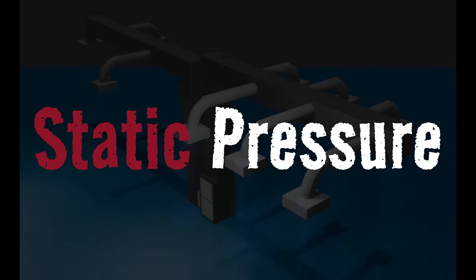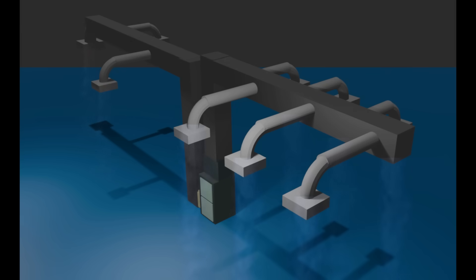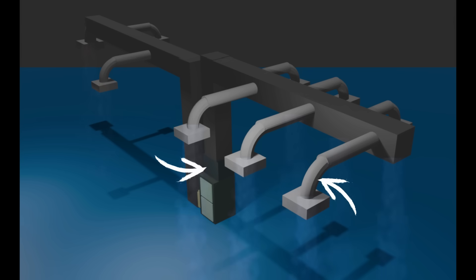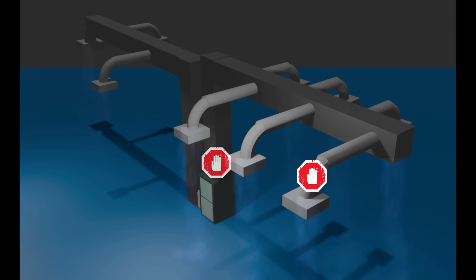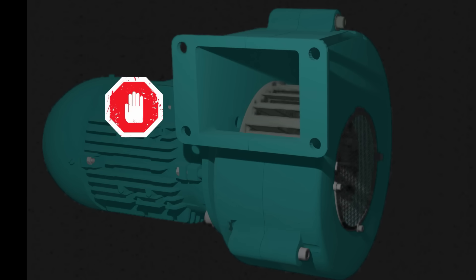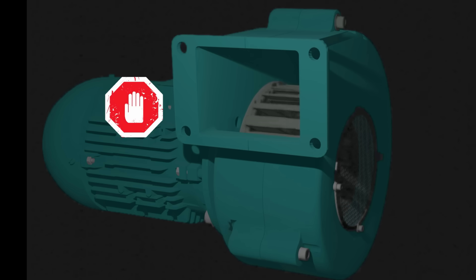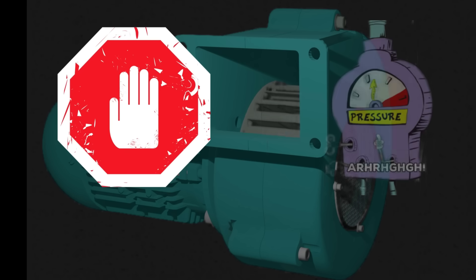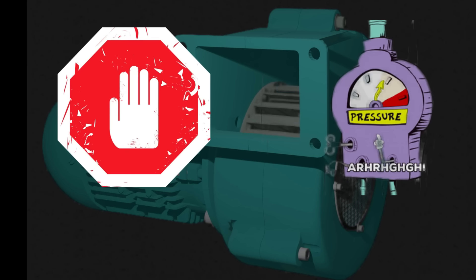The word 'static' in static pressure doesn't mean that the pressure never changes. It just means that the obstacles creating that pressure are fixed in place — they don't move. The bends, the coil, the filter, the duct material — those things are always there, always pushing back against the airflow. The pressure itself can rise or fall depending on how much air the blower is trying to move. The harder the blower pushes, the more those obstacles push back and the higher the static pressure climbs.